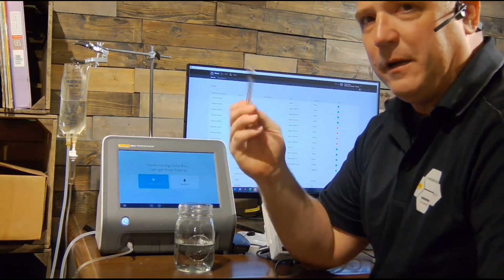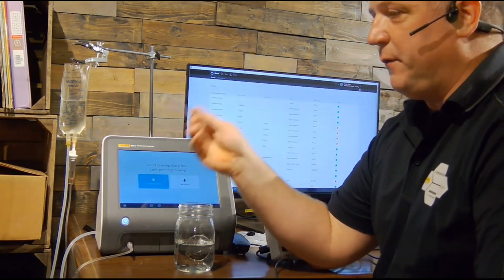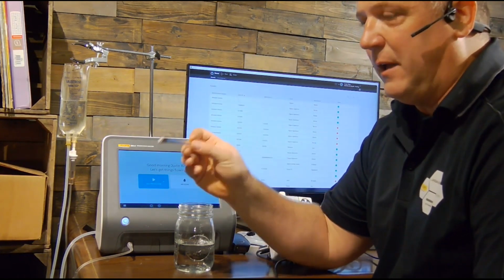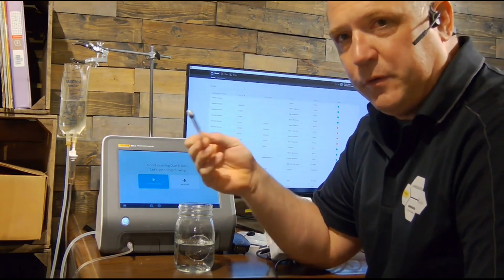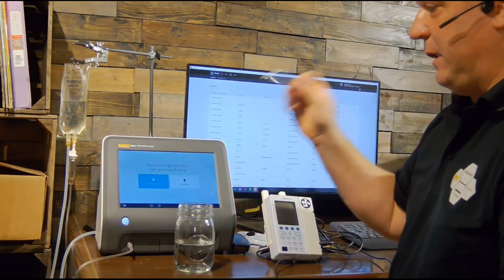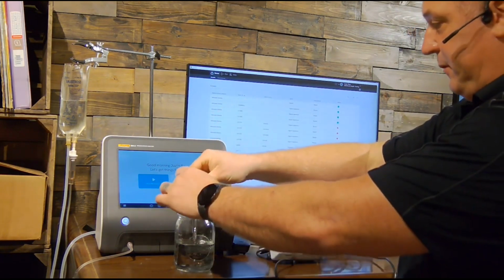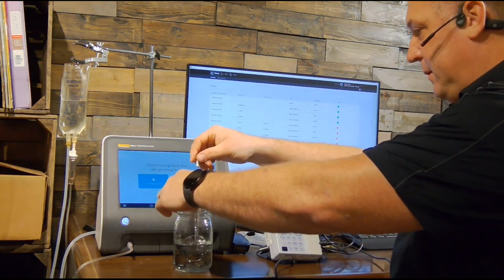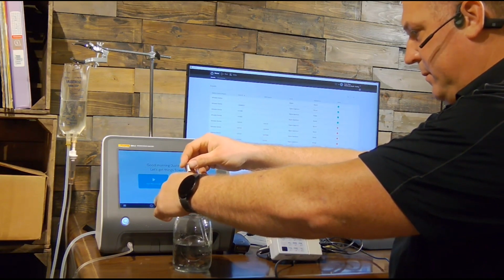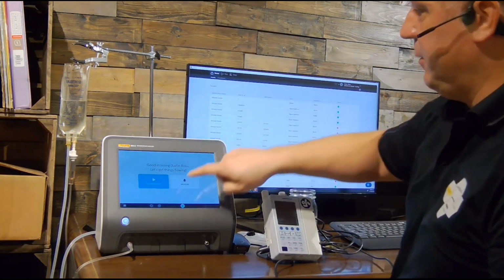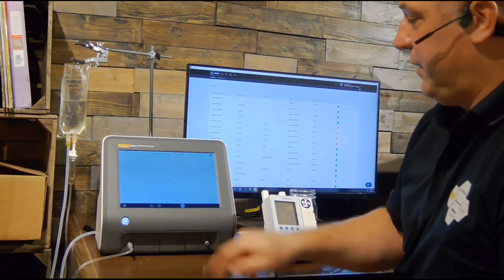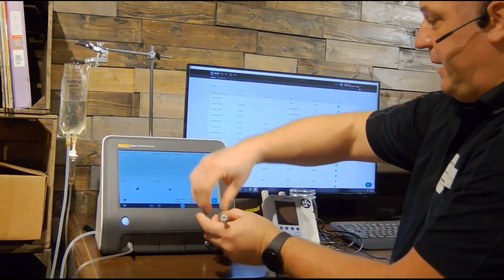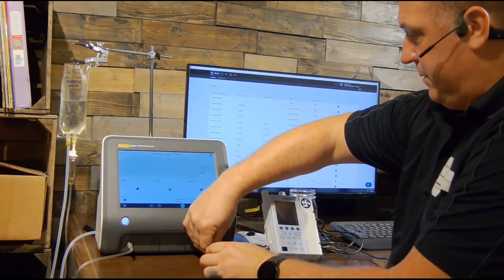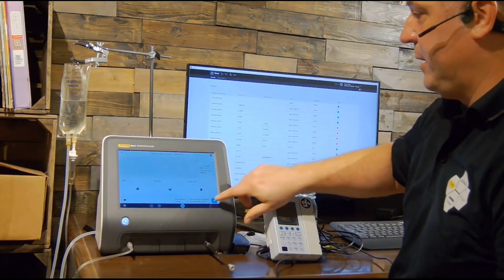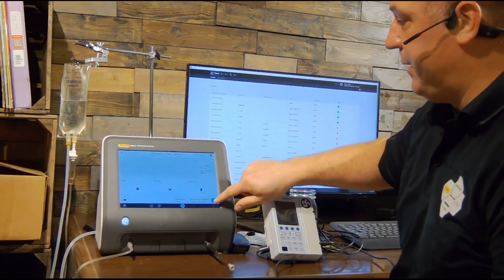Now, you're going to wonder, what am I going to do with these 2 droplets of water? Because a lot of the infusion pump analyzers on the market aren't sensitive enough to pick up that difference of 2 single droplets of water. So let's fill this up again. Here we go. All right. And I'm going to go into manual mode of my IDA-6 on channel 4 here, connect the syringe, and under flow and volume, I'm going to push play.